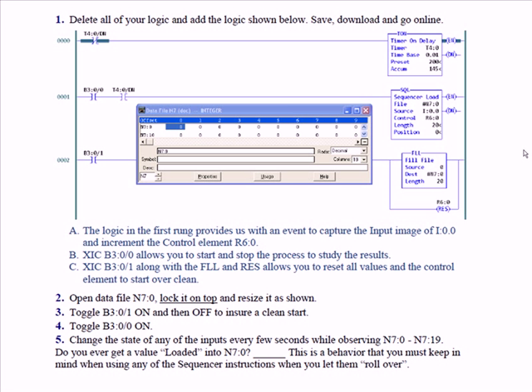And of course, B3:0/1, you wouldn't want that on anyway, because whenever that's on, that's going to fill N7:0 for a length of 20 with zeros. So you're going to cancel everything, clear everything, any time B3:0/1 is on. So really, B3:0/0 controls the sequencer load instruction.